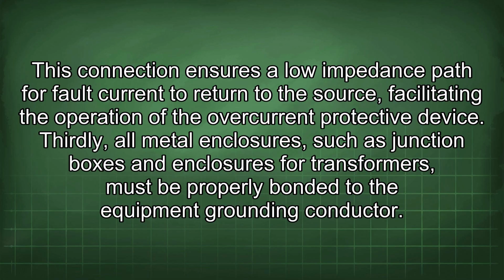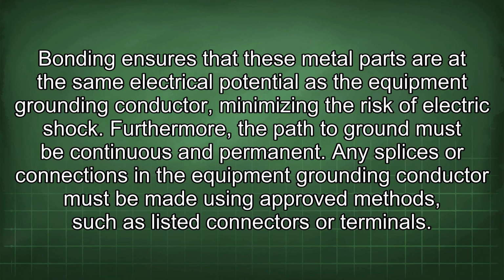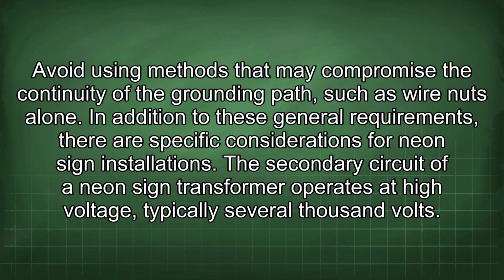Thirdly, all metal enclosures, such as junction boxes and enclosures for transformers, must be properly bonded to the equipment grounding conductor. Bonding ensures that these metal parts are at the same electrical potential as the equipment grounding conductor, minimizing the risk of electric shock. Furthermore, the path to ground must be continuous and permanent. Any splices or connections in the equipment grounding conductor must be made using approved methods such as listed connectors or terminals. Avoid using methods that may compromise the continuity of the grounding path, such as wire nuts alone.